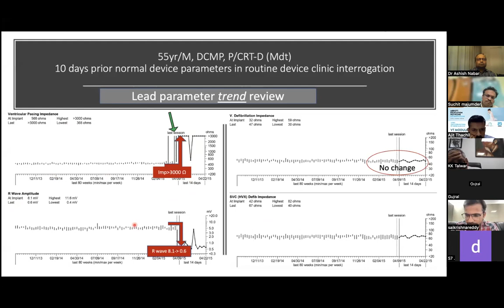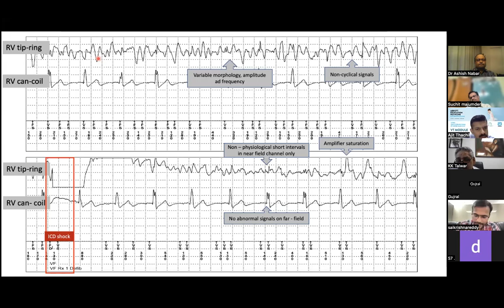So when we analyze the intracardiac EGMs, the top one is RV tip to ring and the second one is RV can to coil, so basically near field, far field, and the marker channel. What we can see here is that the near field is showing multiple signals with variable morphology, variable amplitude, and variable frequency. These were all non-cyclical, which means continuous. And these are also non-physiological intervals. There are almost less than 150 millisecond intervals in the near field channel only, and the far field is clean. You can also see some signals saturating the amplifier. All these five features are features of conductor fracture. And because you are seeing this only in the near field, we can say that the conductor fracture is in the pace sense lead.